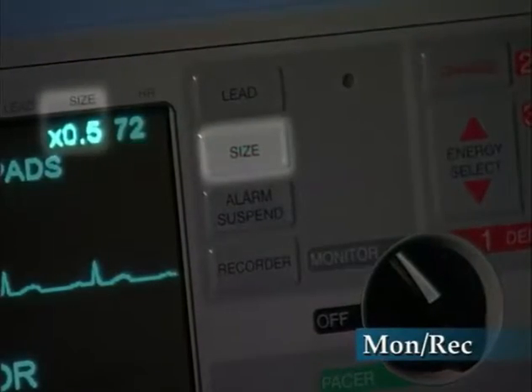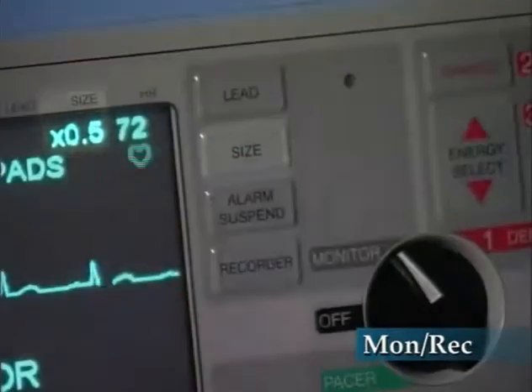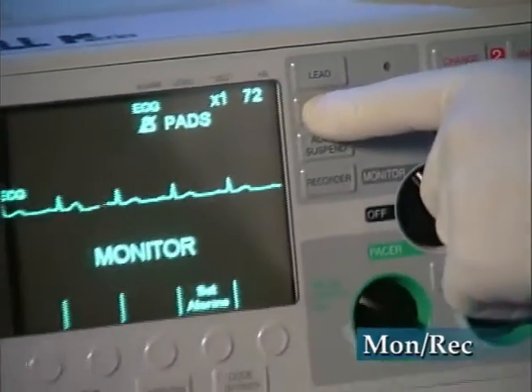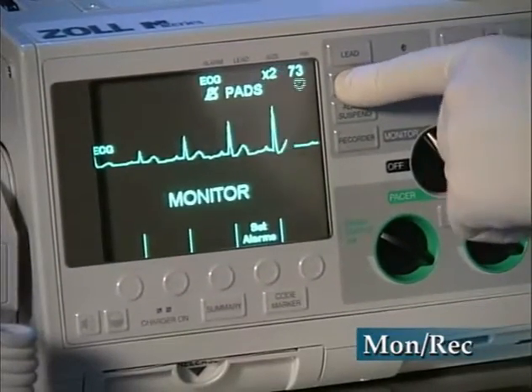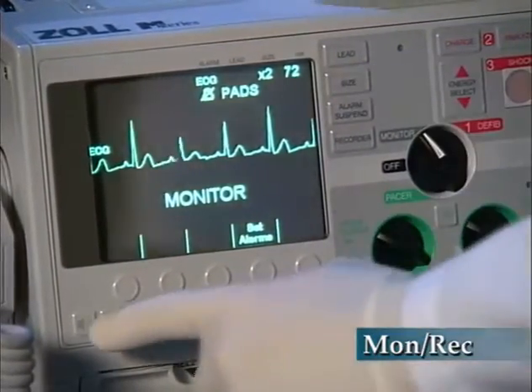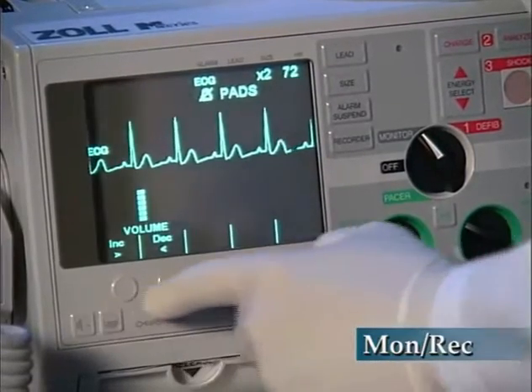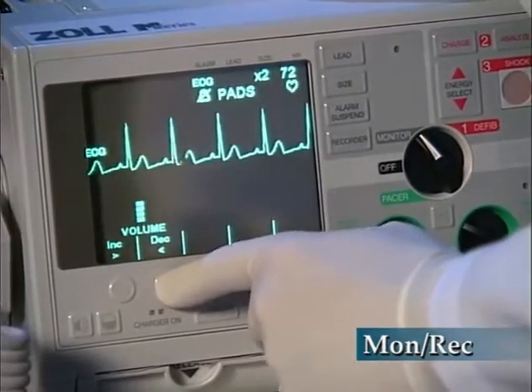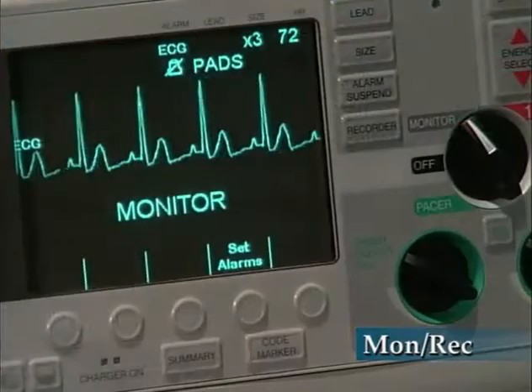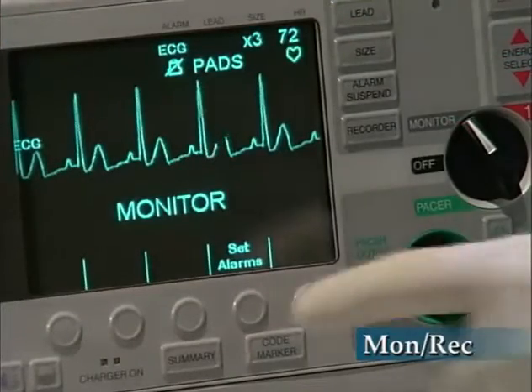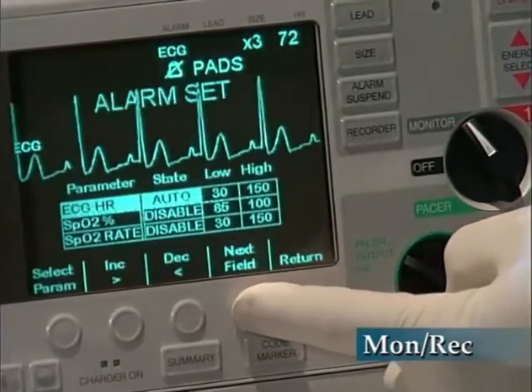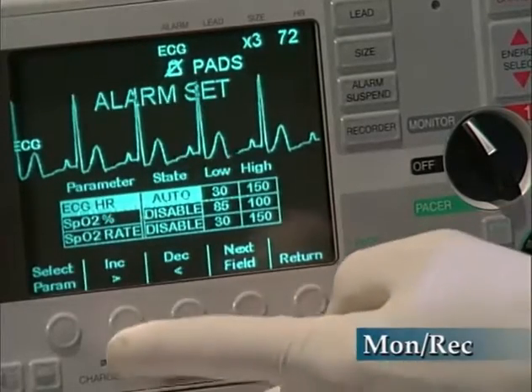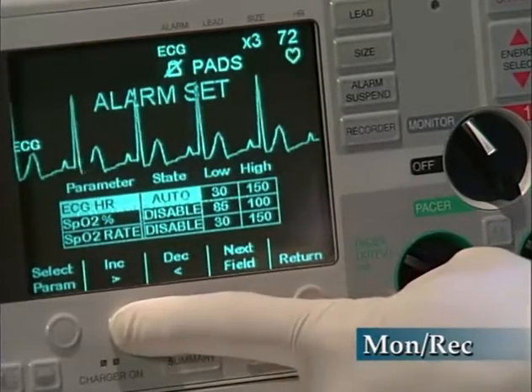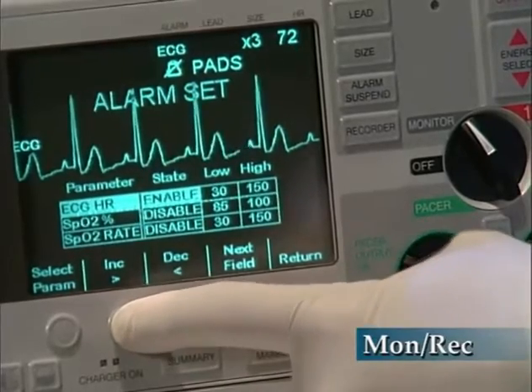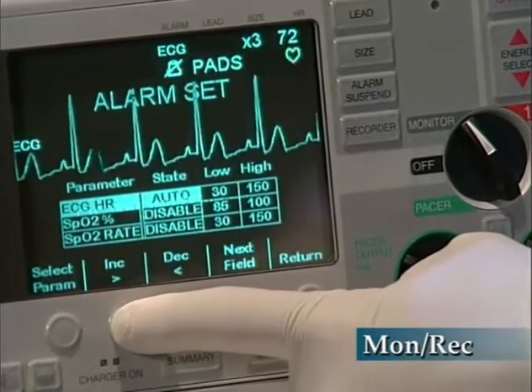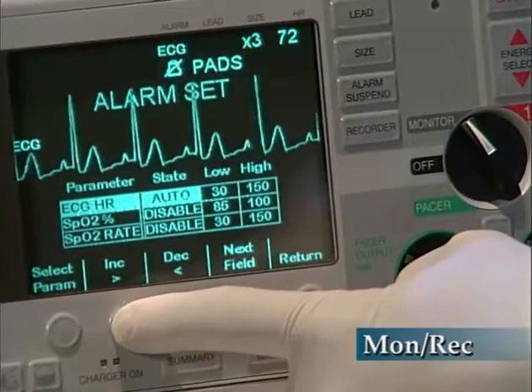The ECG size is automatically set at turn-on. Press the size button to adjust the waveform. The QRS beeper volume can be adjusted by using the speaker button and appropriate soft keys. Default heart rate limit alarms are 30 and 150 beats per minute, with alarms enabled. Preset limits, manually selectable, and auto limits of 80% and 120% of patient heart rate can be selected from the Set Alarm function soft keys.